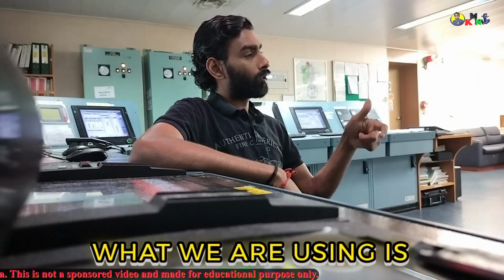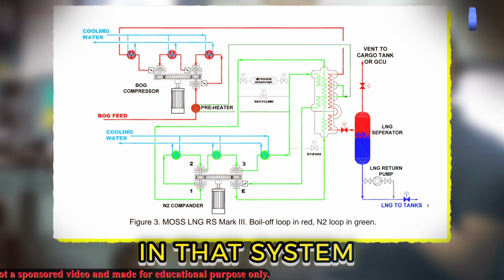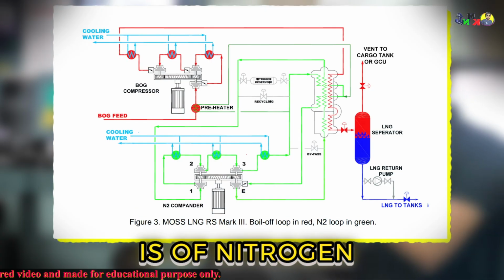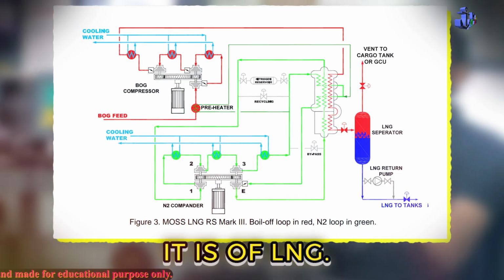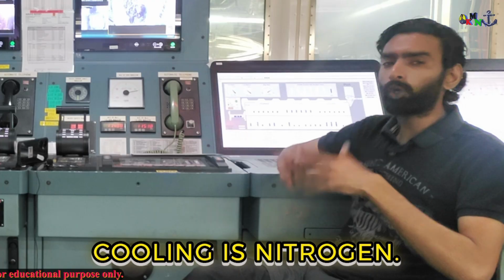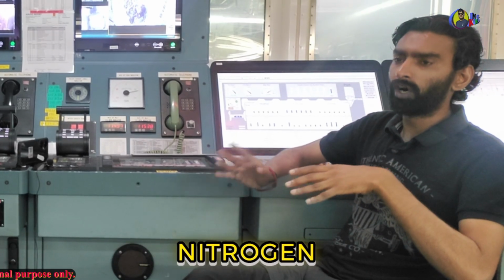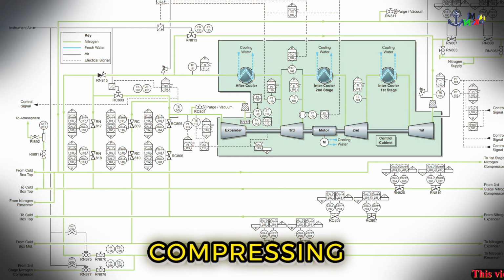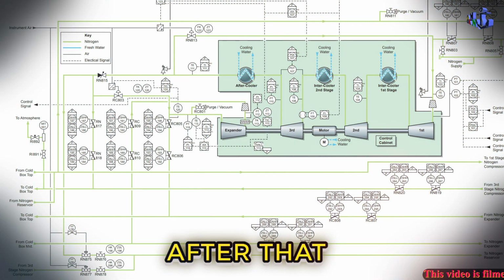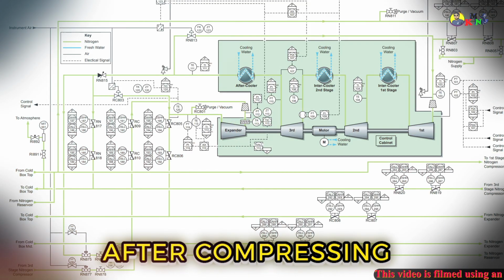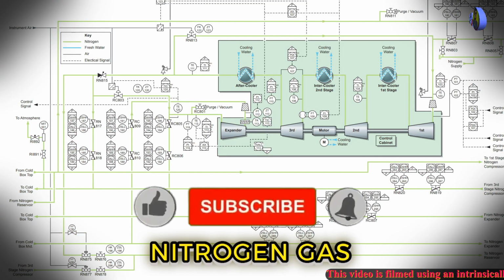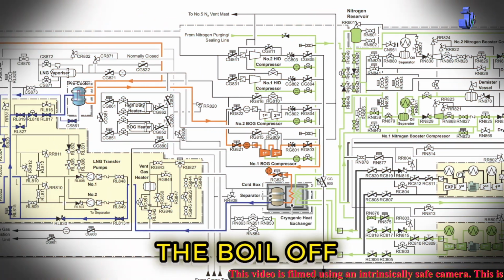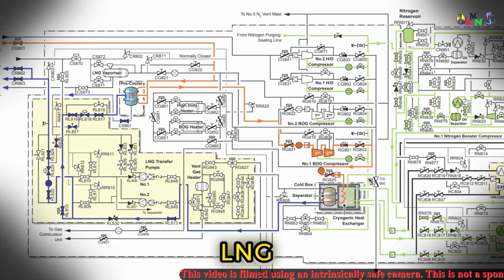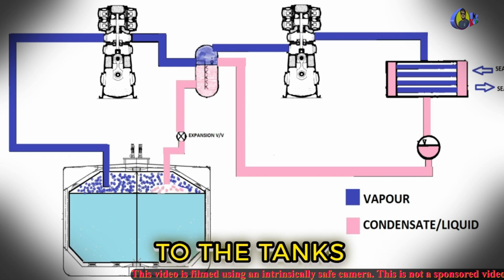Here on board, what we use is nitrogen. In that system, one loop is nitrogen and another loop is LNG, so the cooling medium is nitrogen. For nitrogen, we have a compander with 3 stages - we compress the nitrogen gas in 3 stages, and after that we have an expander. After compressing it in 3 stages, we expand the nitrogen gas, and that cold nitrogen passing through the cold box cools the boil off gas from the tank, which is LNG, and that liquid LNG is put back into the tanks.